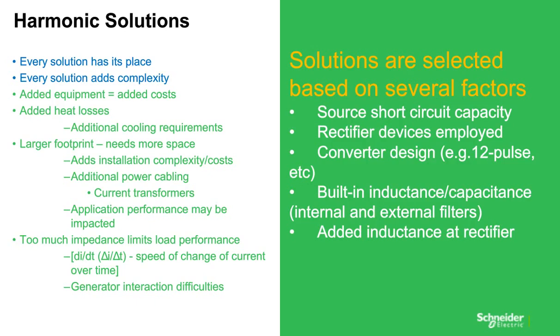Okay, so starting off here with harmonic solutions. Solutions are selected based on several factors, which are short circuit current capacity, rectifier devices employed, converter design, i.e. 12-pulse and 18-pulse drives, built-in inductance, capacitance, internal and external filters, and added inductance at rectifier. And one thing I want to note here is that every solution really has its place per application.